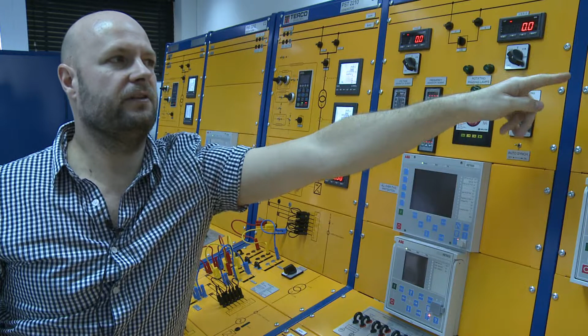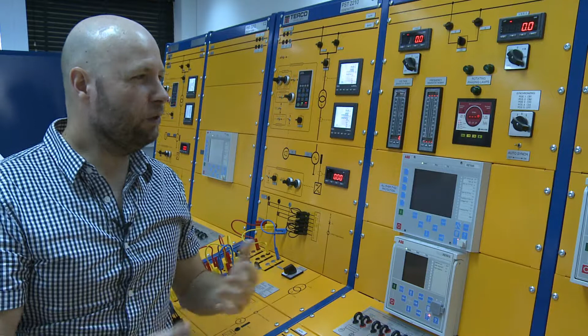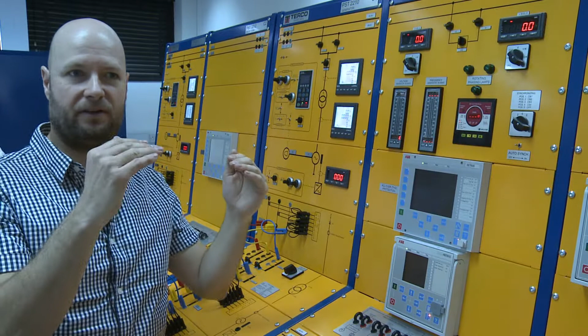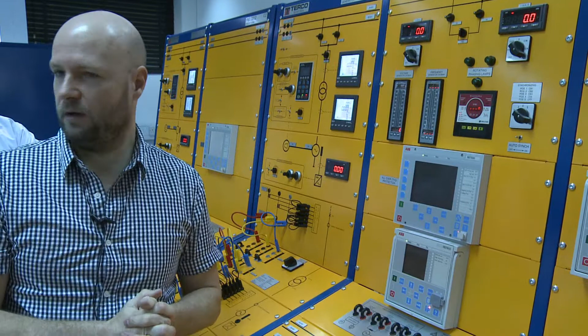But we can also choose to synchronize around CB3 or CB4, and we do that through here. You can do it manually or semi-automatically. By semi-automatic, it means that we can connect everything and tell it to wait for the parameters to be correct. But then we must manually adjust the speed and the voltage. The last step, when you switch on to look at the synchroscope, should be manual, right? We can do both. The last step can be manual or auto.